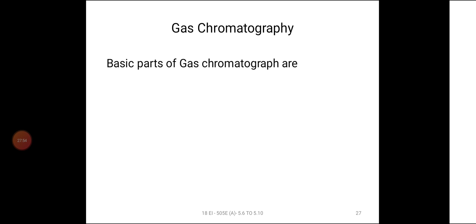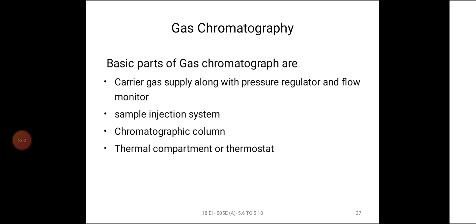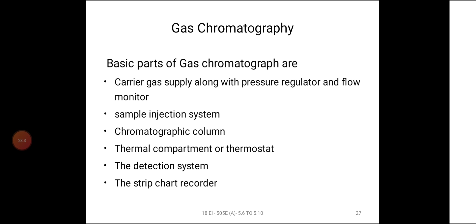So the basic parts of the chromatograph are the carrier gas supply along with the pressure regulator and flow monitor, the sample injection system, the chromatographic column, the thermal compartment or thermostat, the detection system, and the strip chart recorder.